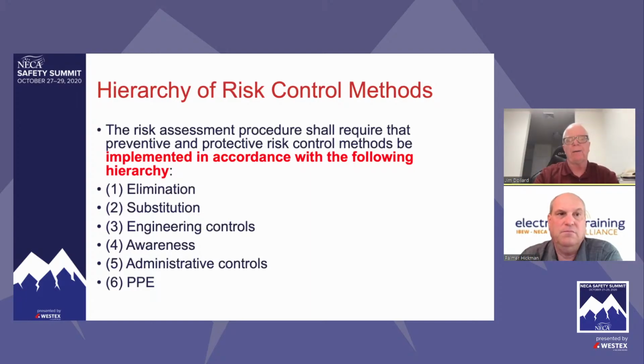This is where the qualified person, that journeyman wireman doing a shock risk assessment or arc flash risk assessment, is trained to go when they determine additional protective measures are required. The first thing they need to consider is elimination. The last thing is PPE.